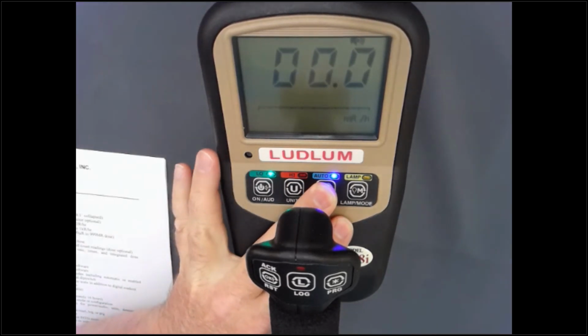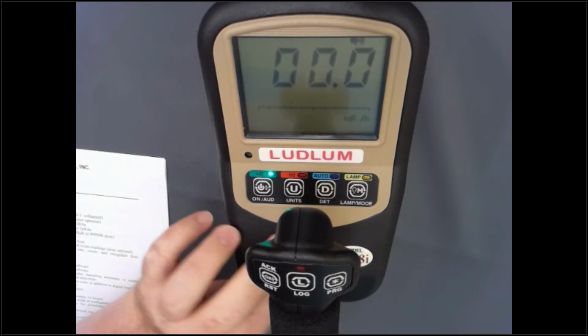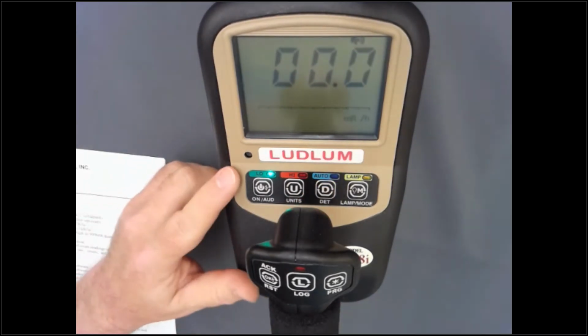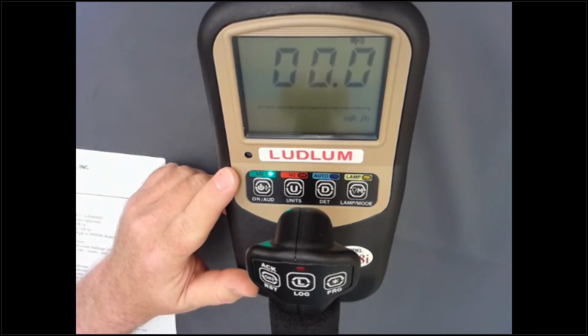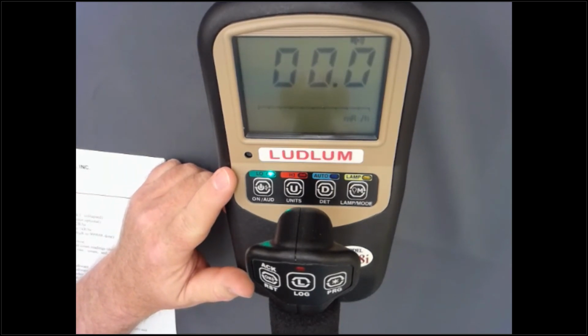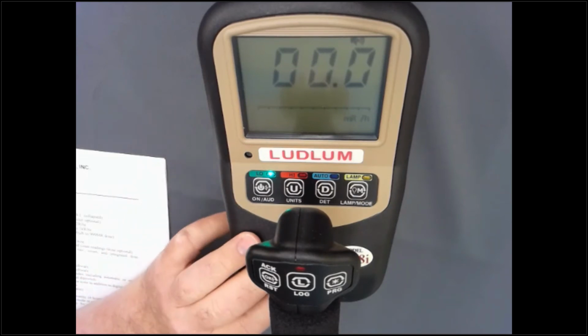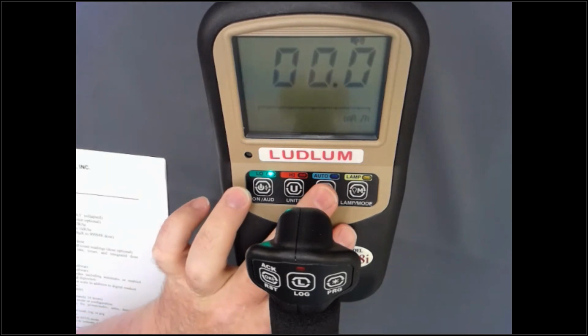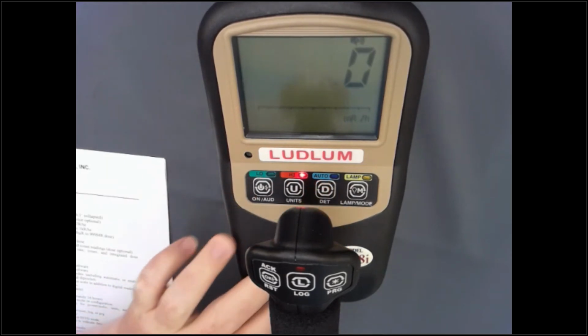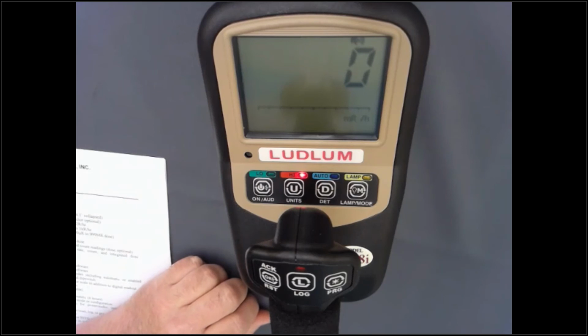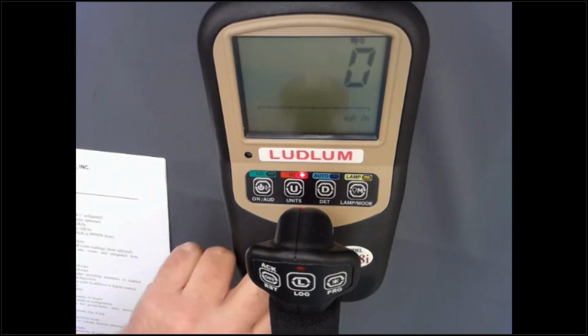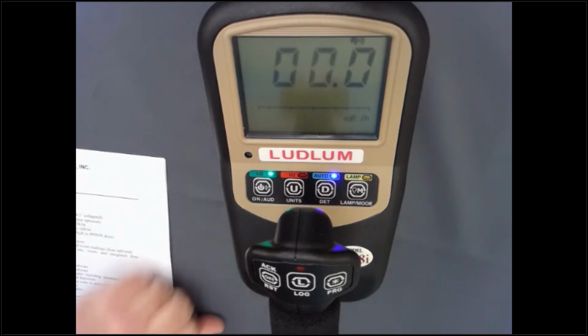A single press on the detector button will generate a single beep. And now we are on the low detector as indicated by the green LED. And from here, you will be able to measure anything from 0.1 mR per hour up to 2 R per hour. If we want to switch manually over to the high range detector, another press of the detector button. And now we're on the high range, where we can measure from 0 mR per hour up to 1000 R per hour. And then we can also go back to auto ranging.